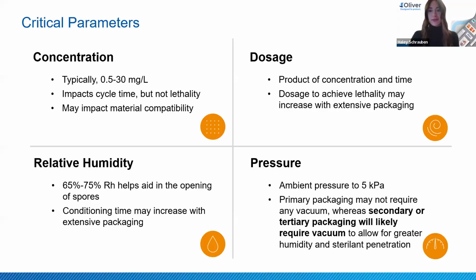Right. Continue on, Emily. So just getting more in depth on the critical parameters that were just in the poll. So with concentration, again, this is going to be what's sent into the chamber. We can fluctuate that. Typically, it can be 0.5 milligrams per liter all the way to 30 milligrams per liter. The main difference is that with a lower concentration, you're going to have a longer cycle time to get to your validated dosage, whereas a higher concentration is going to be a shorter time. There may also be an impact on material compatibility, but that can be tested. And again, that may be based off of your material choices that are used.